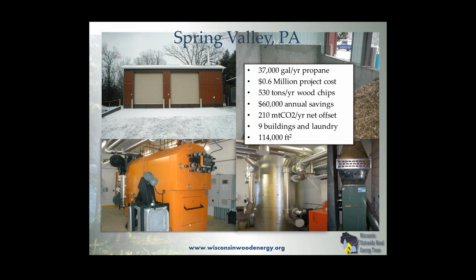What happened was, they put all their pipe in, purchased it from a reliable, reputable company, and they had some punctures in the pipe filled with water, and all the insulating value was gone, and they literally could follow the pipe all over campus. They ripped that out and put in a product that had an injected closed cell foam in the pipe, so there were no voids. If the outer casing or outer protective casing of the insulation was damaged, there was nowhere for water to travel around the pipe.